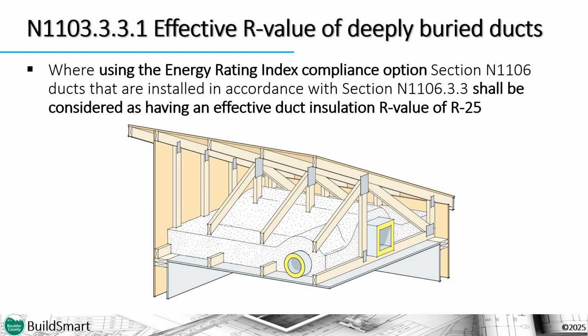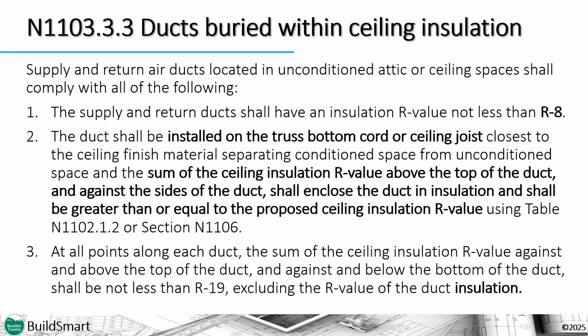So if ducts are deeply buried in insulation in accordance with the code, they are allowed to be modeled as if they were insulated to an R25. However, this installation is difficult and expensive to achieve, and I will speak to that in a moment. This is what burying ductwork in insulation in accordance with the code actually means. So take some time now to read this slide and then start up the presentation again.